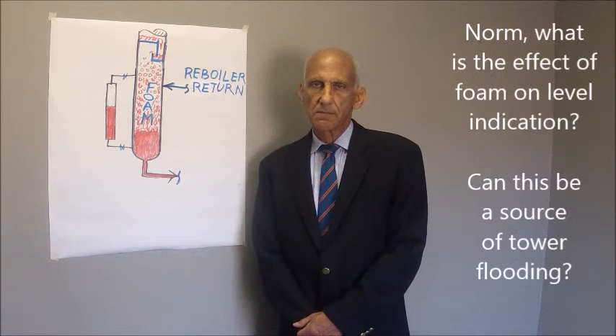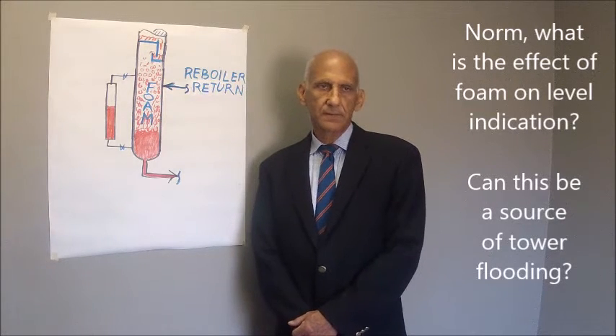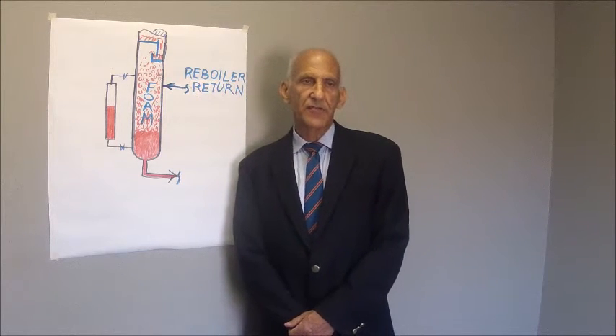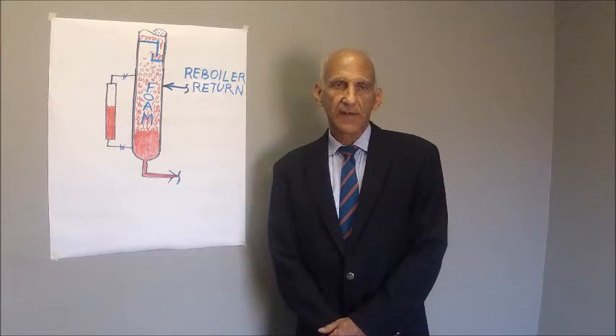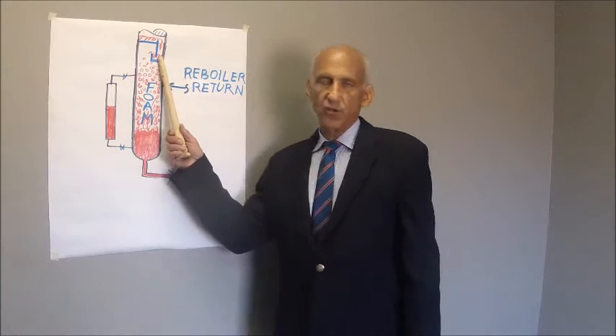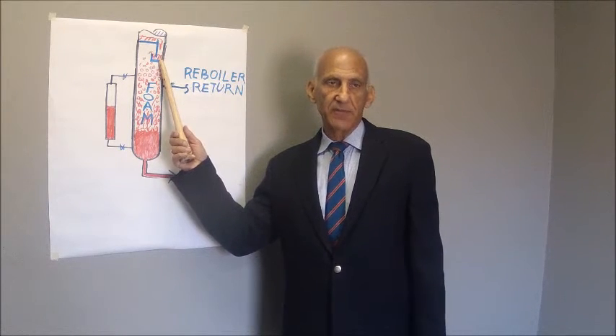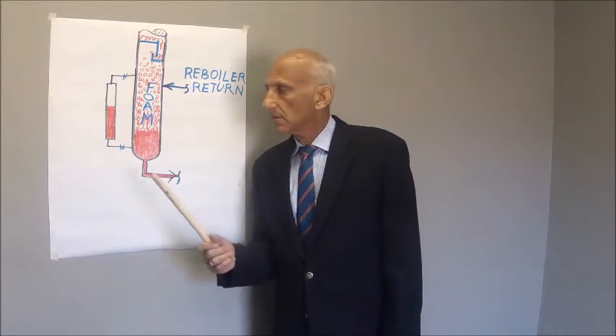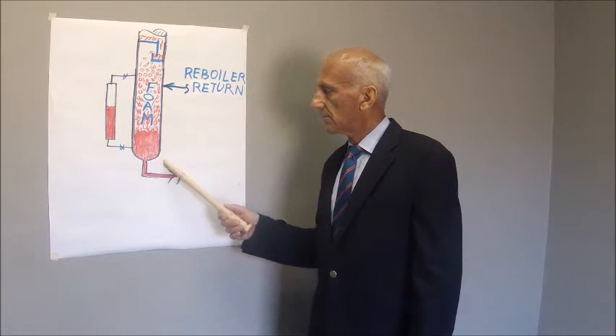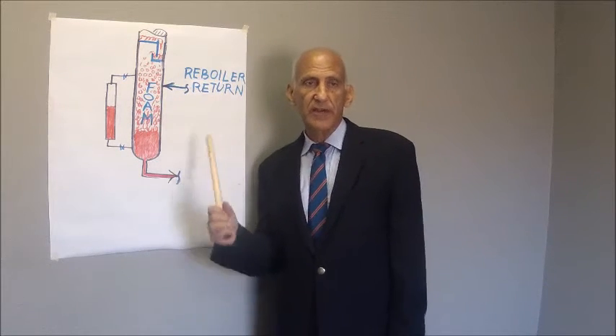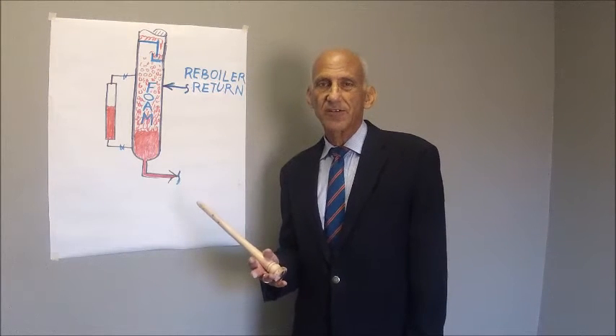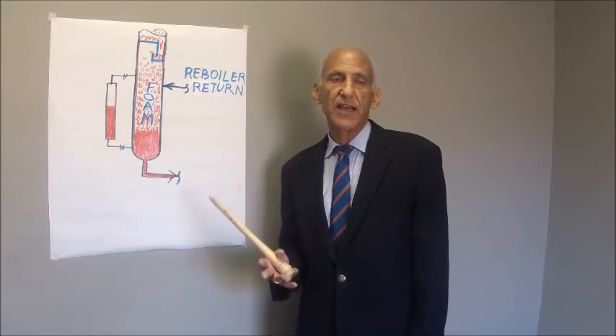Norm, what is the effect of foam on level indication? Can this be a source of tower flooding? Well, actually, foam in the bottom of towers is rather universal. After all, the fluid drained from the bottom tray has just been mixed with vapor, so it's to some extent foam. Also the liquid, if it's coming from a reboiler, will also create foam in the bottom of the tower. So foam pretty much is encountered in many, if not most, towers.